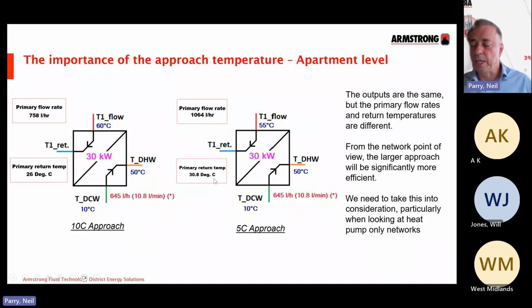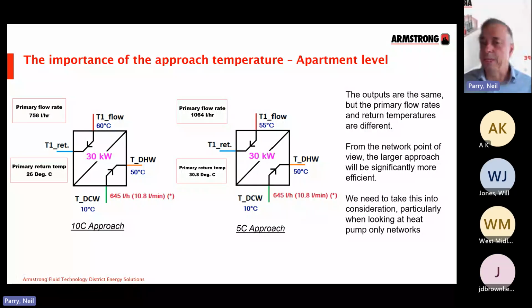Now, the 5-degree for me would be the absolute minimum. In theory, you can use whatever approach you want, and I often get asked, are your plate heat exchangers suitable for a 2-degree approach, for instance? Any exchanger is suitable for any approach, but it has negative ramifications for the performance of the system the more you reduce that approach temperature. So it's something we need to think long and hard about. And for me, I've never normally gone below 5 degrees on typical sizing of a system.